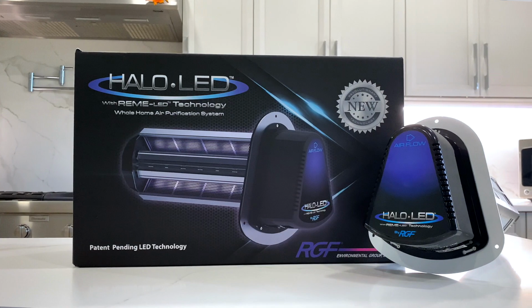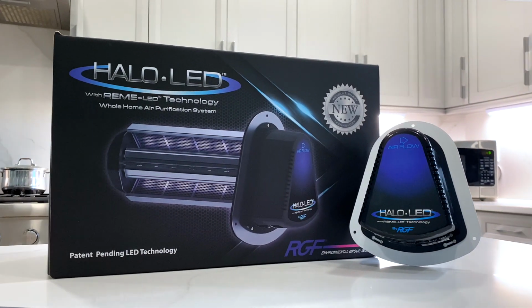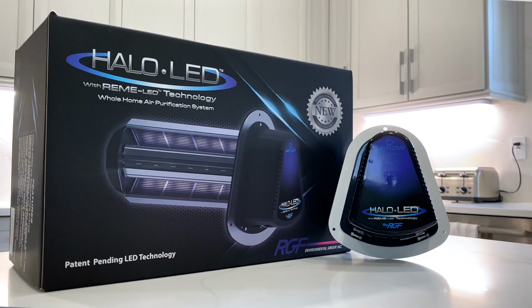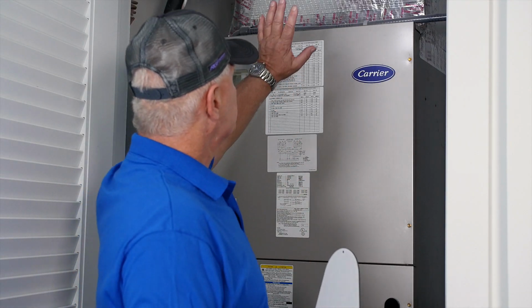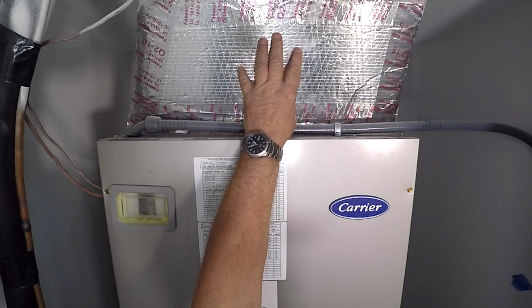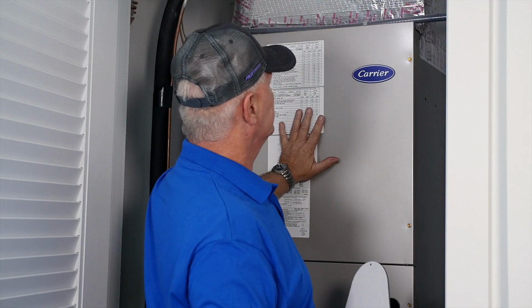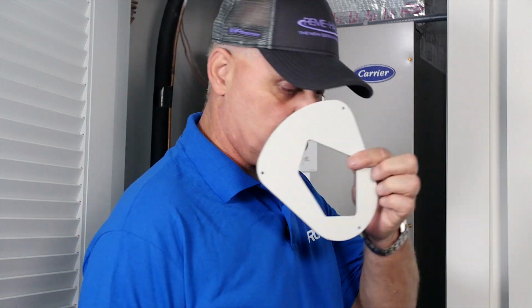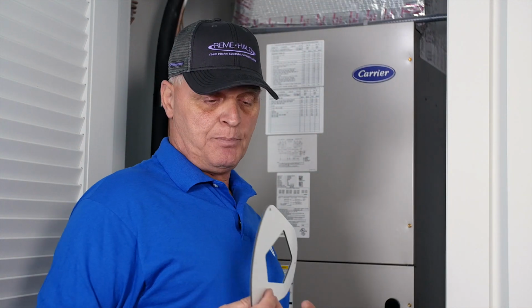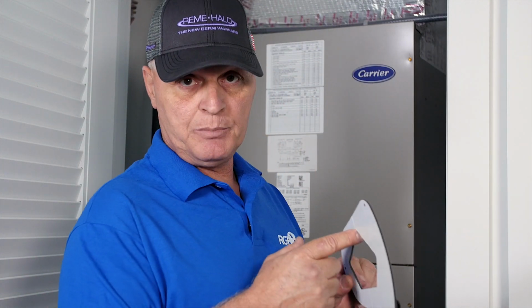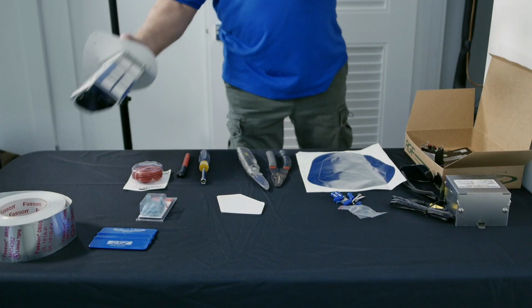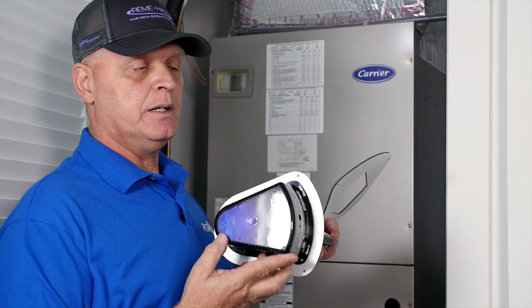Today we are installing the REME LED unit into a standard electric heat air conditioning unit. So the first thing you need to do is mount it into the supply plenum above your air conditioning unit. The LED unit comes with a gasket, but you have to make sure, because the gasket has a certain shape to it, this shape normally wants to have the diamond point up, and you have to pay particular attention to the airflow on the LED unit.